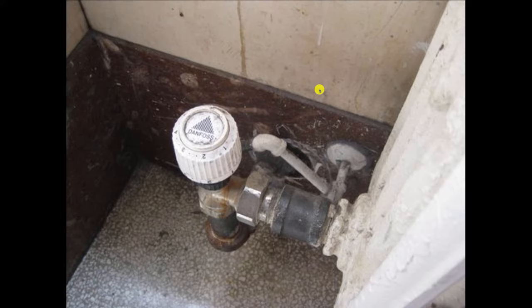Now, this job was having a problem because when the pipe got hot, the heat from the pipe was coming right up into the bottom and causing the valve to close. That's why they got it set on 5, because the radiator valve was shut on the temperature of the heat in the pipe. So the way this was fixed was we exchanged this self-contained head for a remote sensing head that could sense the temperature somewhere else, you know, put it over here on the wall where it's not going to feel the temperature of the very hot pipe.